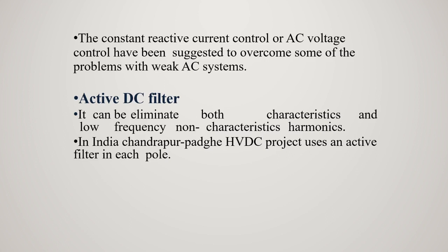So the active filter can eliminate both characteristic and low frequency non-characteristic harmonics. Both Siemens and ABB have supplied active filters. In India, Chandrapur Padghe HVDC project uses an active filter in each pole.